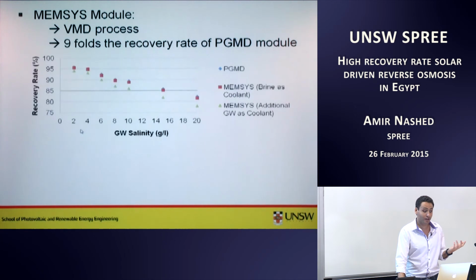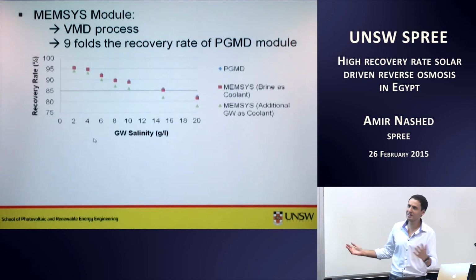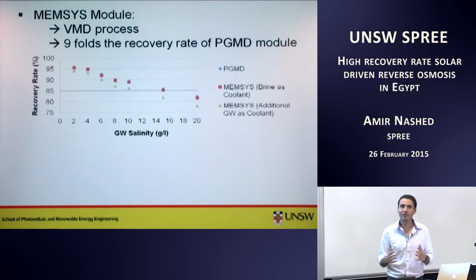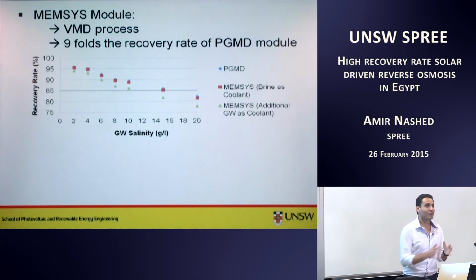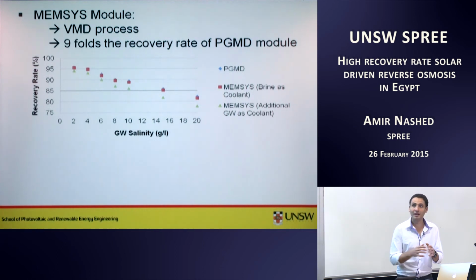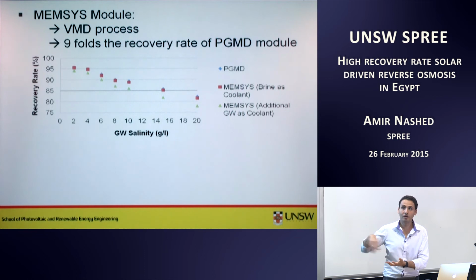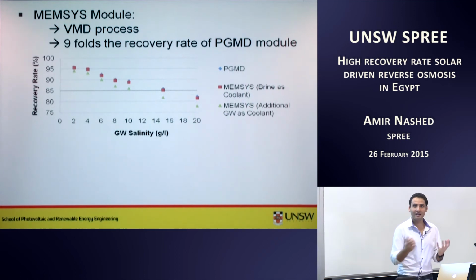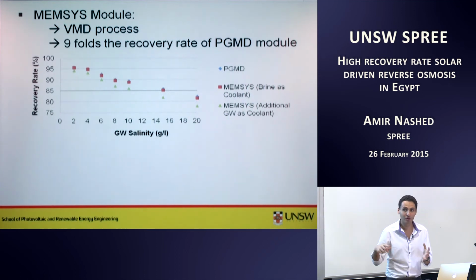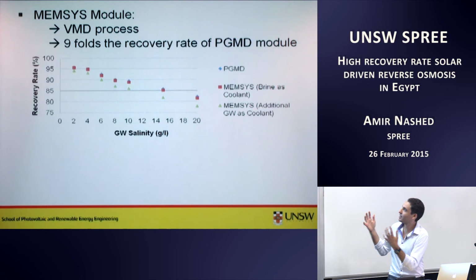When I investigated the maximum recovery rate, I found it was still lower. How come? What I found out is this module, although it has higher recovery rate, uses a separate channel for the coolant, and the coolant flow rate required is 9 times the feed flow rate. And this coolant water again has to go through the cooling tower, so we still have the same problem, and that's why I got a similar recovery rate.